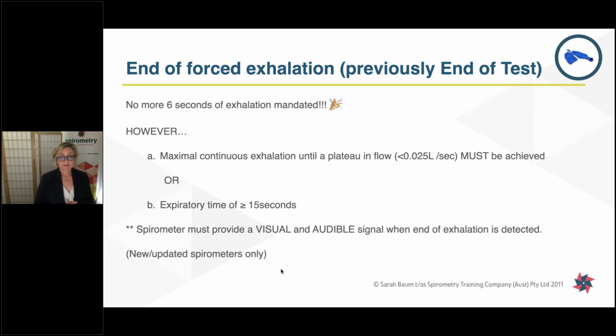However, it's still got to be observed that they get to their end of exhalation, and that's by observing the plateau. So we're looking at that volume time curve, and we must be able to confirm that there's a plateau before you can end the test. When your software is updated, or if you purchase a new device, you'll get an audible or visual signal when the end of exhalation is detected based on that plateau. And what the sensor will determine is when there's been no change in volume for a second.